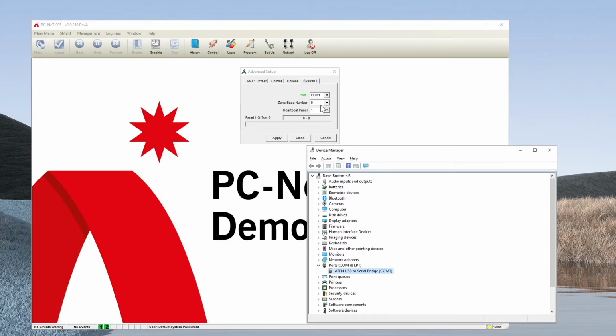The port speed needs to be set to a setting of 38400 bits per second. Nothing else should be changed and press OK. Then within the PC-Net-005 application, we simply select COM port number 3, click apply, and communications will then start between the application and the BMS interface.